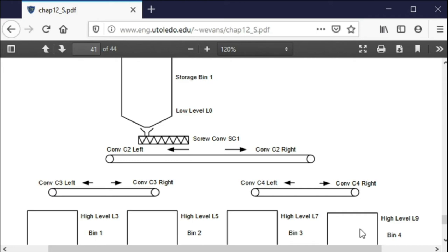Because you write the logic in order, don't you? You write it first, then second, then third, then fourth. If you write it so that as soon as the one is satisfied and you go to the next one, let's say this one is the one that is being serviced. Let's say this one goes empty, but this one had already gone empty. You're going to service this one before you do this one, because your logic for this is ahead of the logic for this one. You see what I'm saying? It precludes the idea of who got there first. It just says, because I wrote this logic next, it hits here, and then it precludes this one, and it precludes this one. So this one may be over there starving while you're always satisfying this one. Not fair, is it? No.